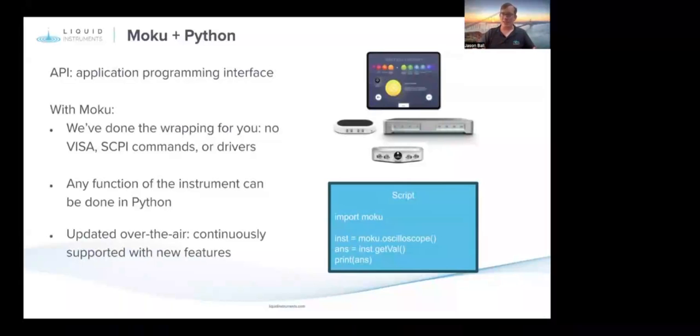So you see there's like a sample script on the right here. All you do is simply import the Moku module and you can start communicating with all of your instruments right away. We've done all of the wrapping up of the commands for you. There's no VISA drive, there's no VISA required, no SCPI commands, no drivers. You simply install the Moku package and you're ready to go.